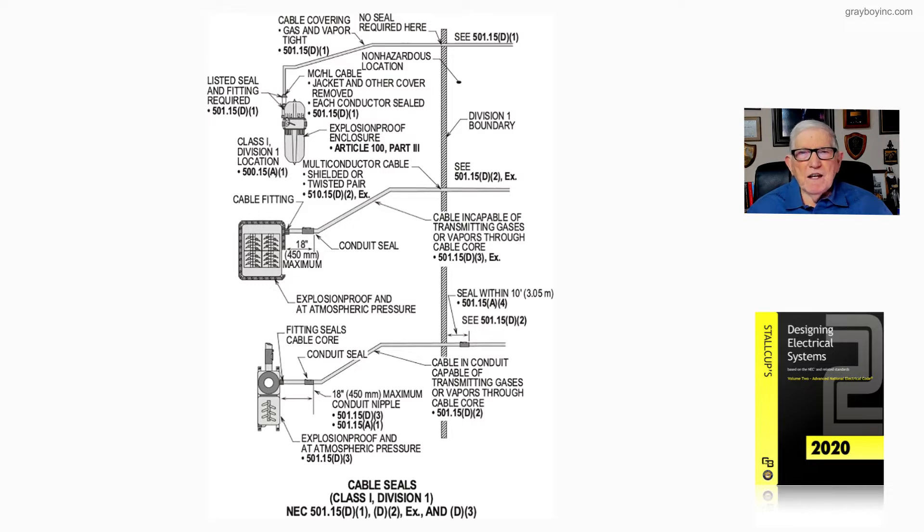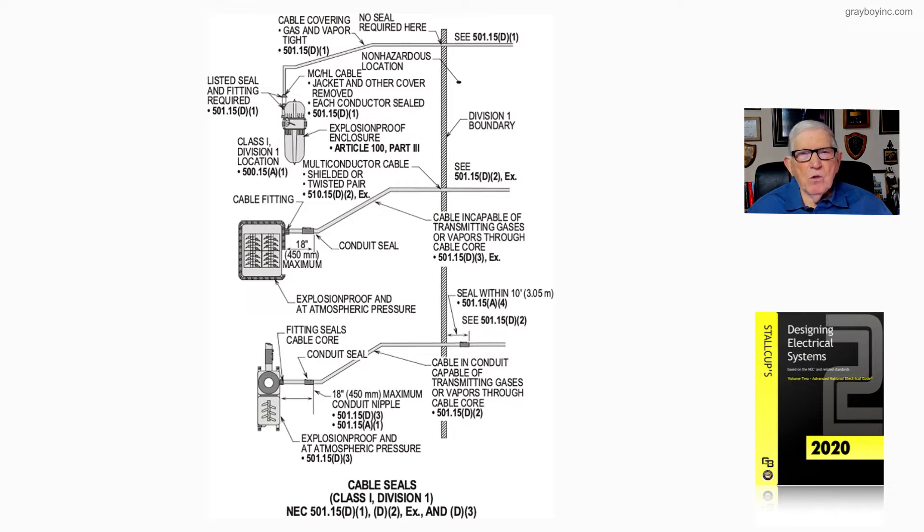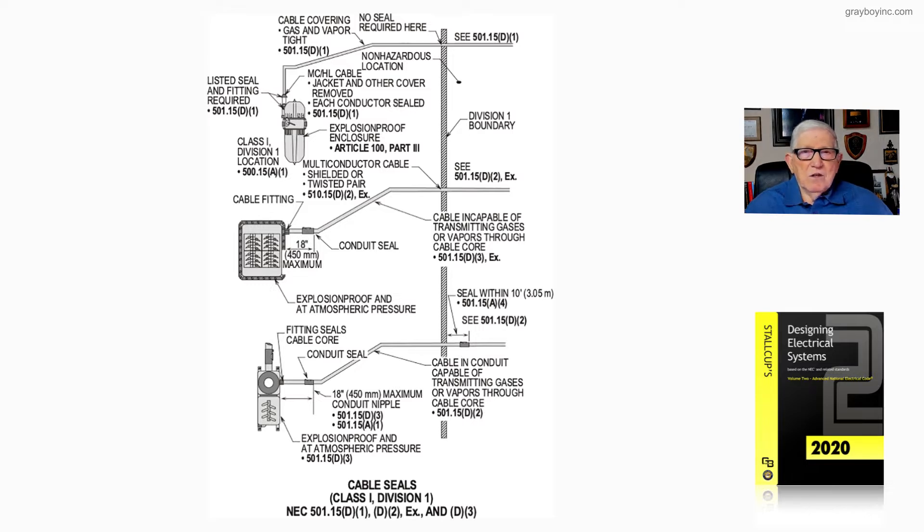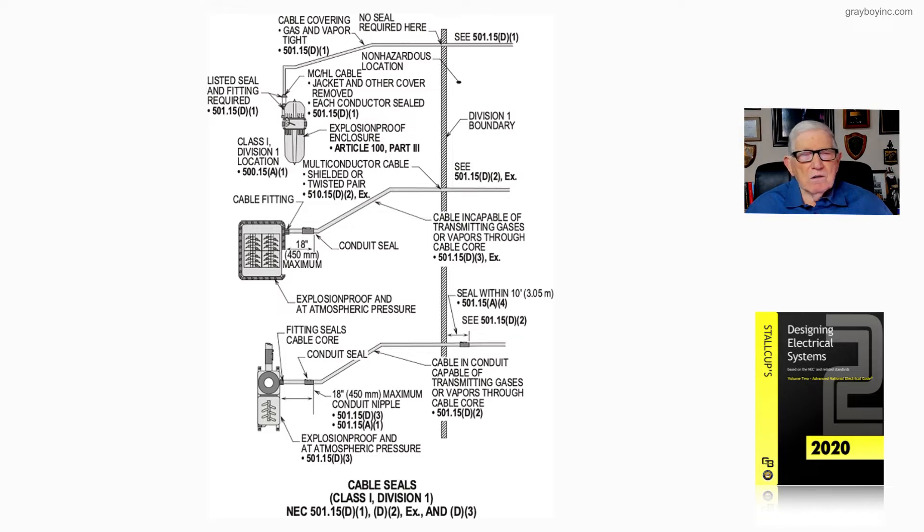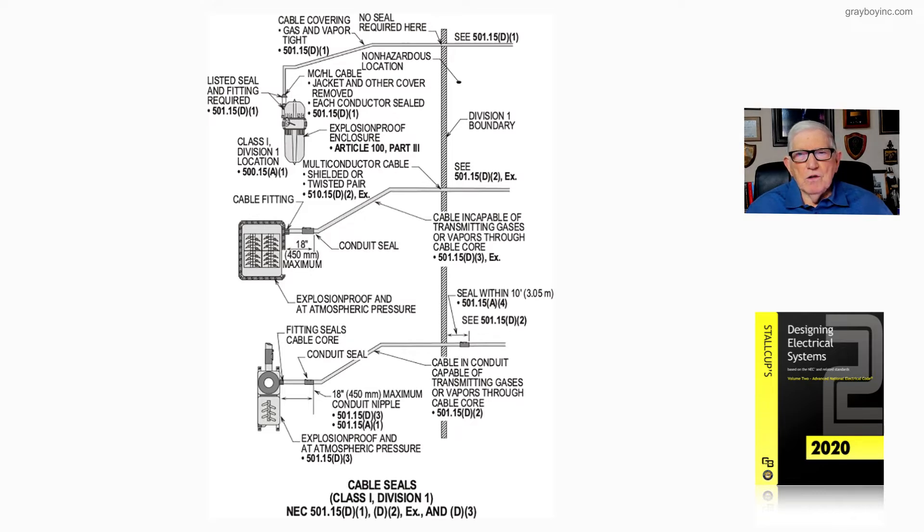When the jacket is removed, we seal around the core and use a special sealing boot inside our compound to seal the core. Once the installation is complete, we haven't entered any classified area or left any classified area until we terminate from point to point.